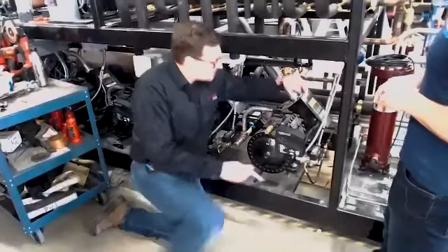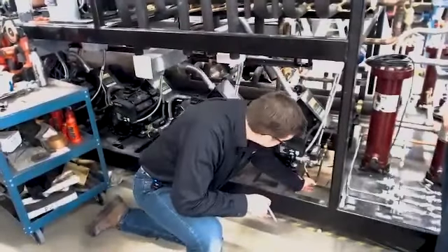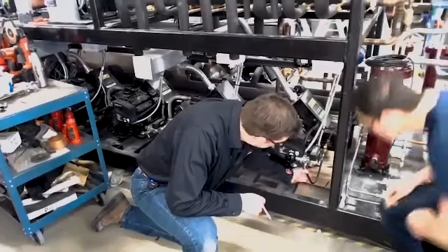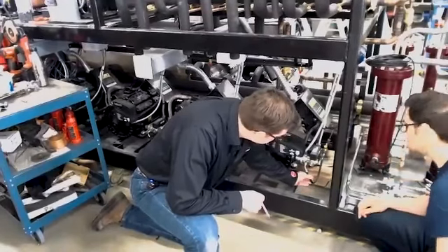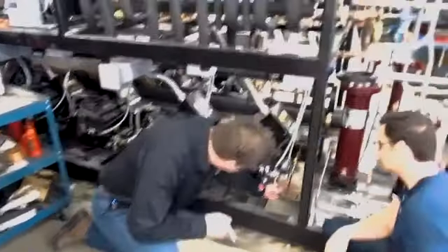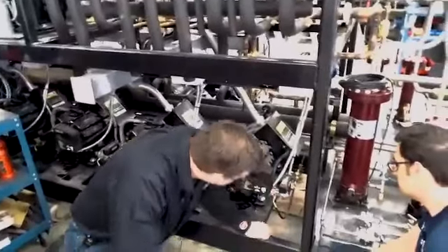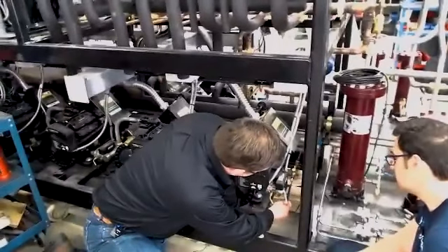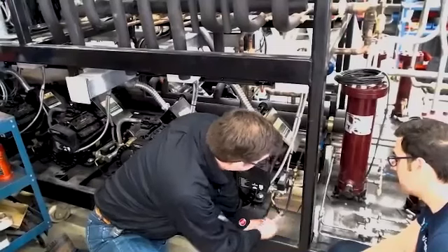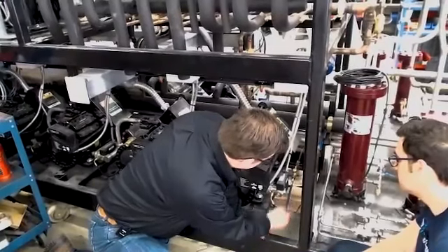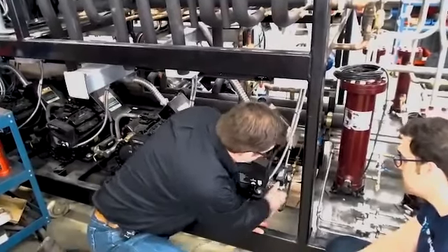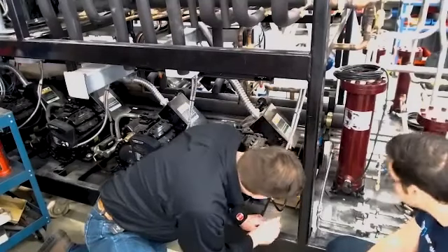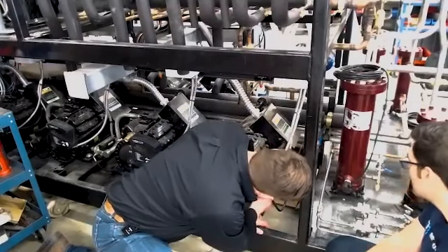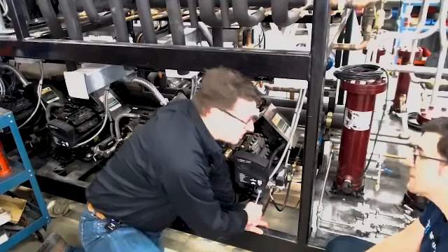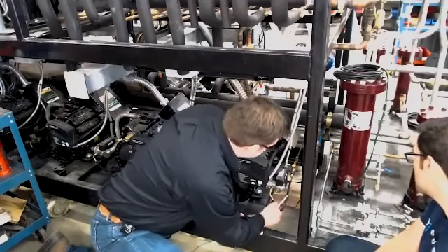Just another note of something some of you guys may see that's different - these are Quadra hoses. This is a high pressure hose, this is your oil feed line. You can see here's my oil regulator, we've got an OMC right here, so you can tell an OMC from an OMB. Quick thing is I've got two sight glasses right here, slightly bigger, high pressure, up to 1,800 pounds. I've got my adapter - you're always going to see us putting in the proper adapter. This gives a little more room to play with.